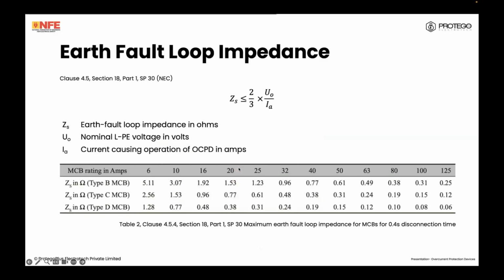So, when it comes to earth fault loop impedance, clause 4.5 of section 18, part 1 of our National Electrical Code of India says ZS, which is your earth fault loop impedance, shall be less than or equal to 2 by 3 multiplied by U0 divided by IA. We're just basically seeing this is a voltage across the circuit. This is the current causing the operation of the OCPD, the instantaneous operation. And we're assuming a safety factor of 0.66 just to ensure that we leave a buffer.